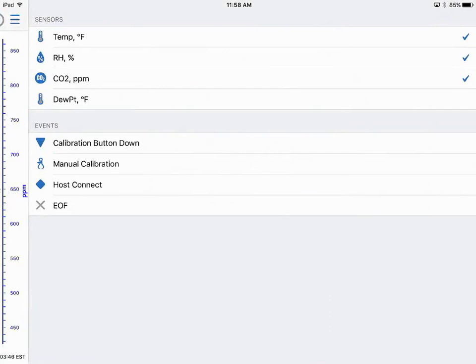This is where I can select if I want to see dew point. Dew point's calculated by the app, so we can click on that. And again, these are my internal events, just like HOBO with their UX products. It keeps track of internal events, like when we calibrated the device, when manual calibration happened. So we can click on to show those, because I did do a manual calibration during this deployment. We can also select to show when the calibration button was pushed, if the USB host was connected, and when the end of file marker was written.